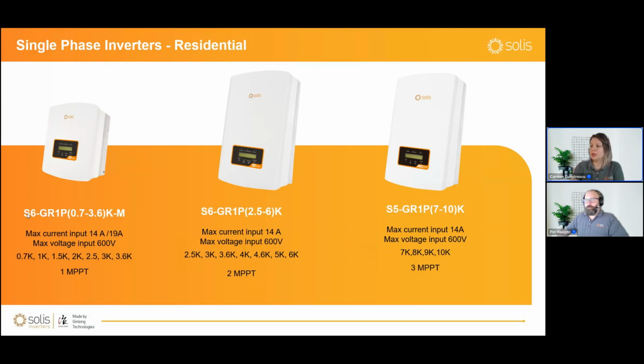We do have the bigger sizes from 2.5 up to 6 kilowatt. These are with 2 MPPTs. You see that they miss the M at the end, so this gives you a hint that there are 2 MPPTs, and we even have a 3 MPPT for those products which are dedicated mostly for the UK market, the ones from 7 up to 10 kilowatt single phase.